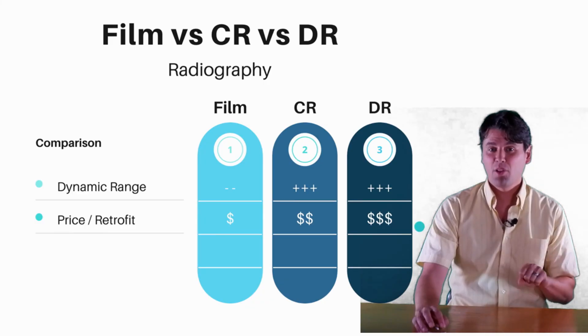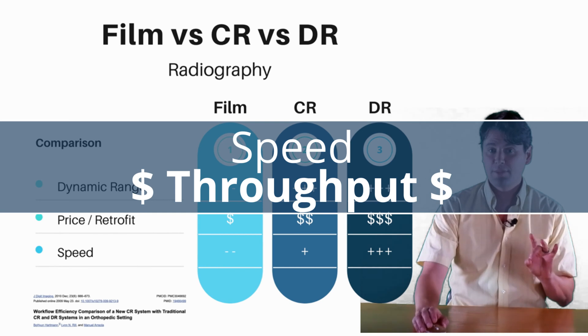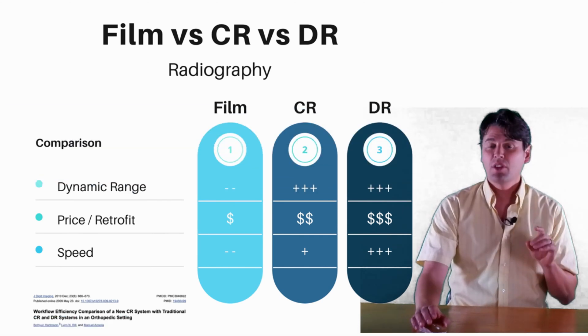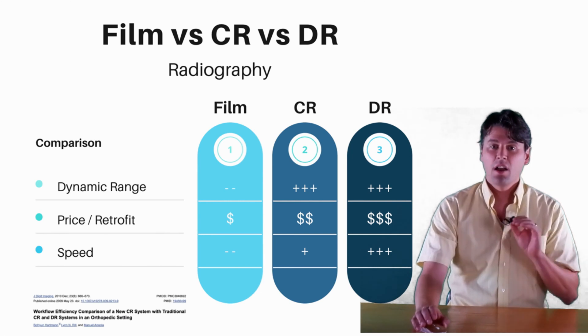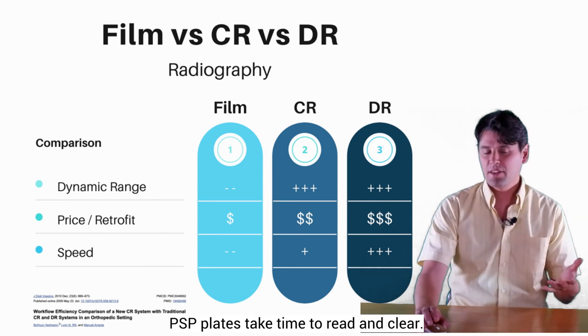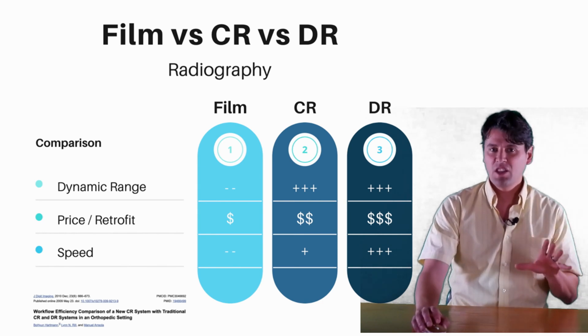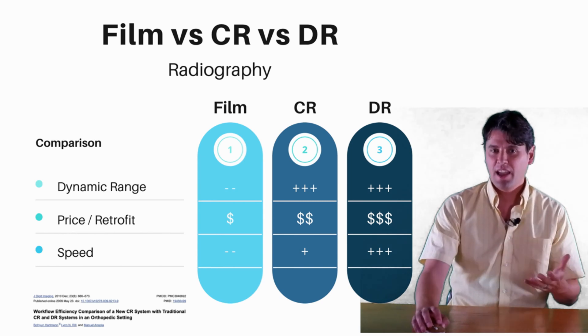We know that DR is going to be the most expensive, but as far as speed DR is definitely going to win the race. There's been a number of studies — here's one example which showed that for a single technologist using standard CR techniques, a standard exam was taking 14 minutes, versus 8 minutes with DR technology. This is because the image can be acquired directly; there's no need to clear the panel. In general, DR is going to be the fastest way to make images, which is a big advantage especially in high-throughput sites.